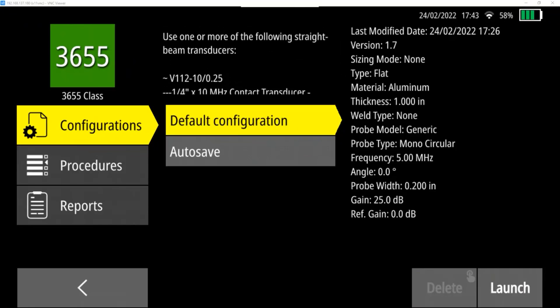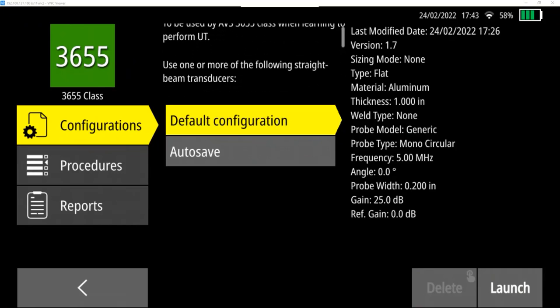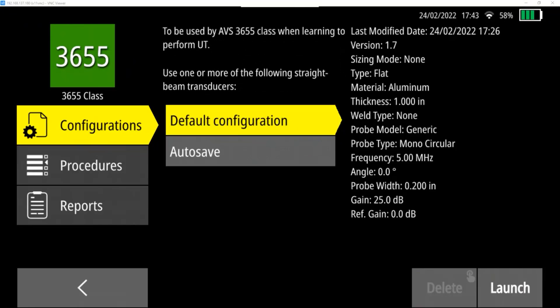There's a list of configurations here. The default configuration are the default settings for all the different parameters that were loaded. And a summary list is to the right. So you can see this one's designed primarily for aluminum material, although you can change anything to use it on steel or any other material. Pre-programmed thickness starts at one inch with no welds. The generic probe is a monocircular probe, the transmit-receive probe. Default frequency, five megahertz. Angle is zero for straight beam, transmit-receive, pulse-echo mode. Probe width or diameter is defaulted to 0.200 inches with a gain set at 25 decibels and a reference gain set at zero decibels.